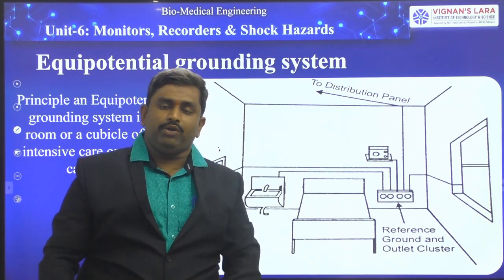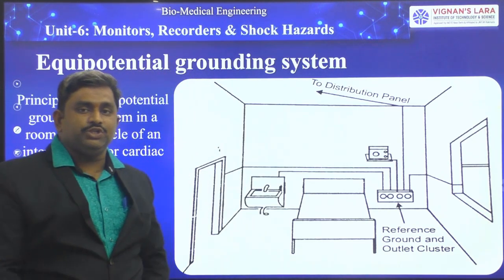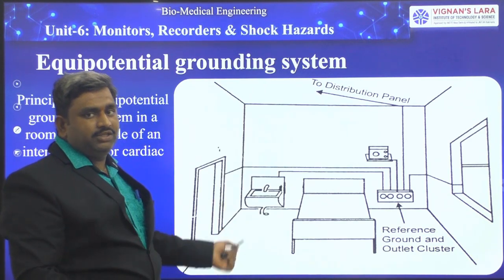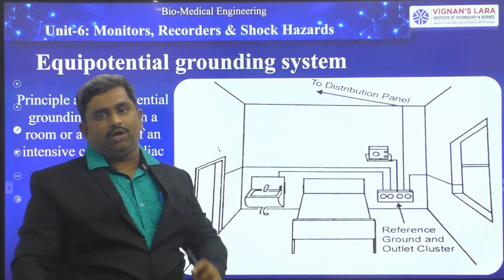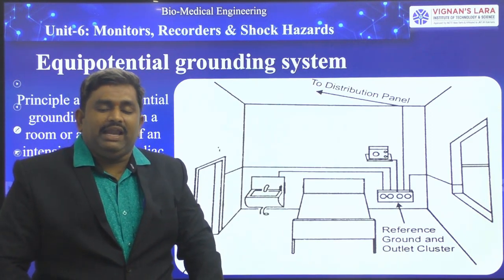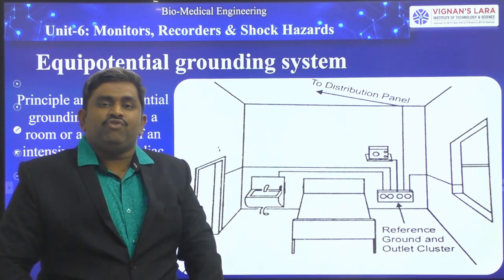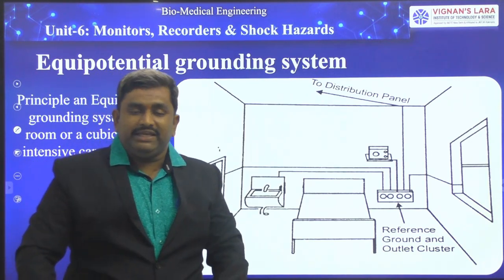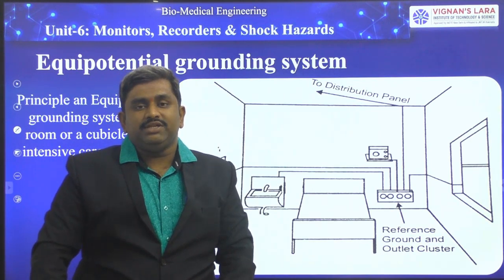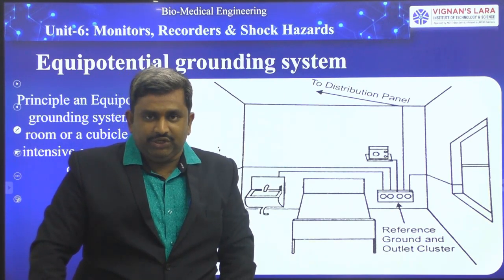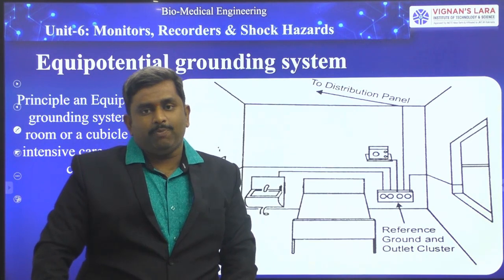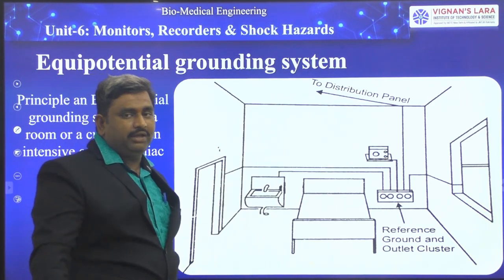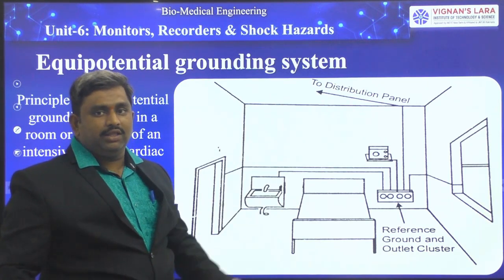This is equipment where you are going to measure some of the physiological parameters from the human body. Now this is an ICU room. In this ICU room there may be a chance of getting electrical accidents from other normal electrical equipment. So the ECG machine we have designed with a perfect isolation strategy, and the human body connected parts we have provided with good safety by using the current limiters. What about the remaining electrical equipment which is available in the hospitals?